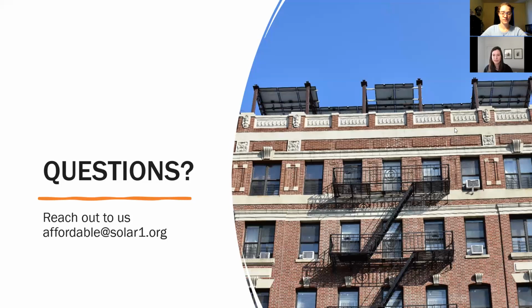Have you worked with solar pavers? Annika, you may have more experience with that. I have not. We haven't worked with solar pavers. They're one of those building integrated PV systems that seem really great in concept and in practice tend to not work very well. If you think about pavers, people walk on them. They get a little bit more abuse than a usual solar panel, so I wouldn't necessarily recommend that unless and until someone can really prove them out as a good alternative.